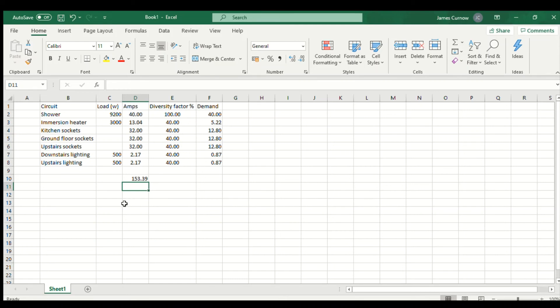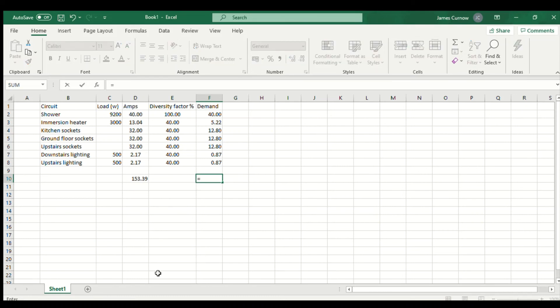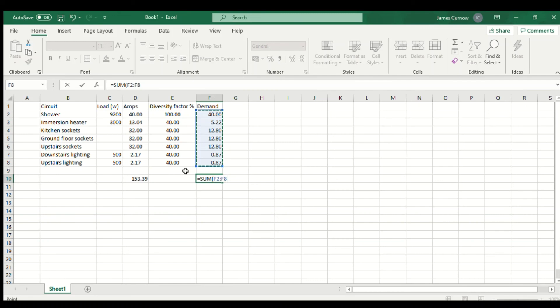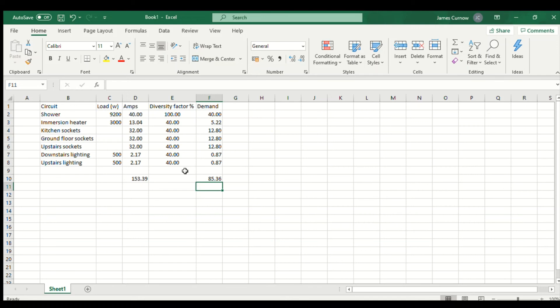That gives us the maximum demand without diversity. As you can see, 153 amps is a lot, so we need to have that diversity applied to bring that down. We're going to do the same thing here, equals SUM and then brackets, click and drag, and that takes us to 85 amps which is much better.